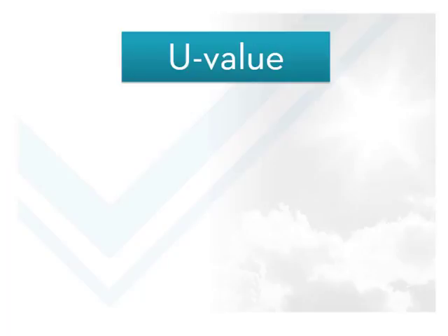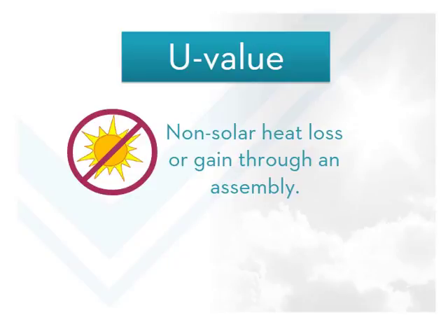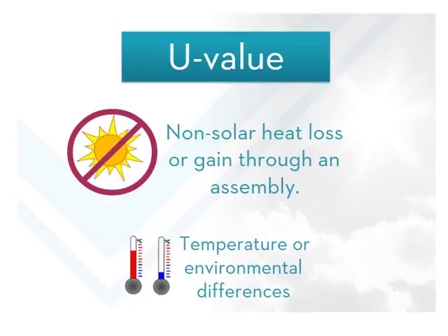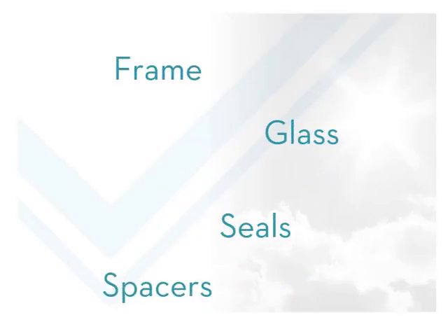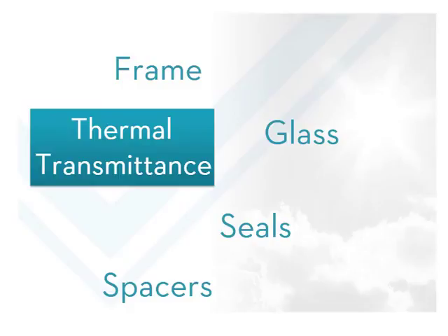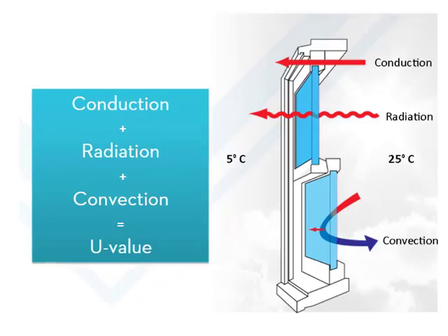What is U-value? By definition, U-value is the measure of the rate of non-solar heat loss or gain through a material or assembly due to the differences in temperature or environmental conditions between the inside and outside of the window. The rate of heat transfer is indicated in terms of the U-value of the window assembly, which includes the effect of the frame, glass, seals and any spacers. Simply put, it's a measure of thermal transmittance — how well a window product prevents heat from escaping by factoring in the combination of conduction, radiation and convection.